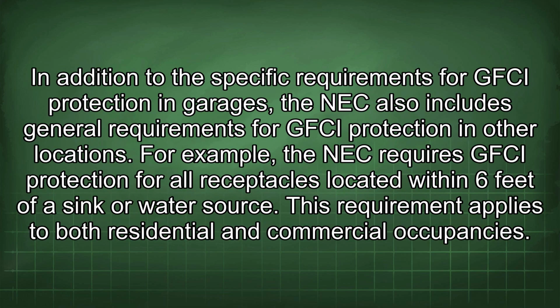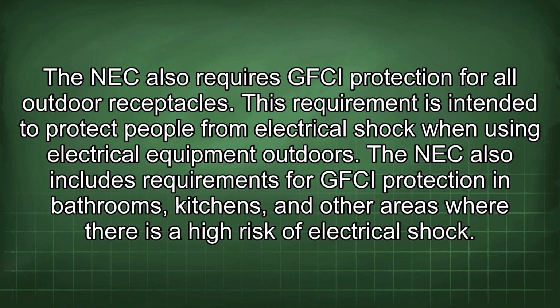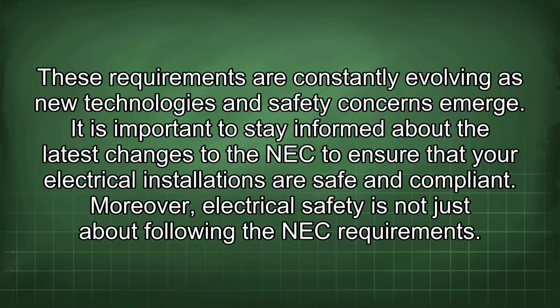In addition to the specific requirements for GFCI protection in garages, the NEC also includes general requirements for GFCI protection in other locations. For example, the NEC requires GFCI protection for all receptacles located within 6 feet of a sink or water source. This requirement applies to both residential and commercial occupancies. The NEC also requires GFCI protection for all outdoor receptacles. This requirement is intended to protect people from electrical shock when using electrical equipment outdoors. The NEC also includes requirements for GFCI protection in bathrooms, kitchens, and other areas where there is a high risk of electrical shock. These requirements are constantly evolving as new technologies and safety concerns emerge.